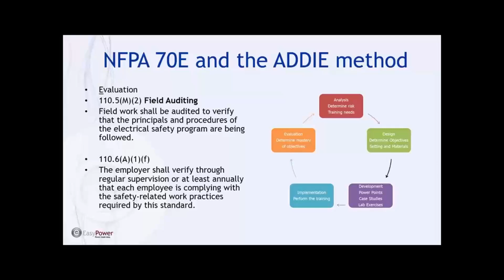Now we're right back to our analysis, because what we're supposed to do when we perform our field audit is collect this data. Hey, we're not using our gloves when we're inside of the restricted approach boundary. We're not performing the live, dead, live, phase-to-phase, phase-to-ground test properly. We identify where we have this gap in knowledge by performing the field audit.